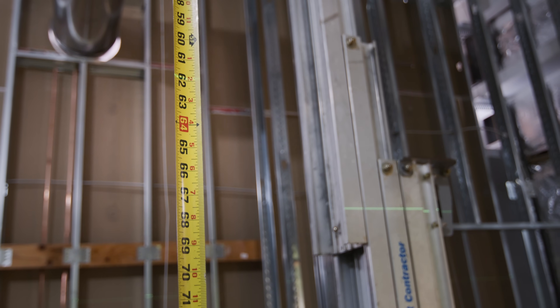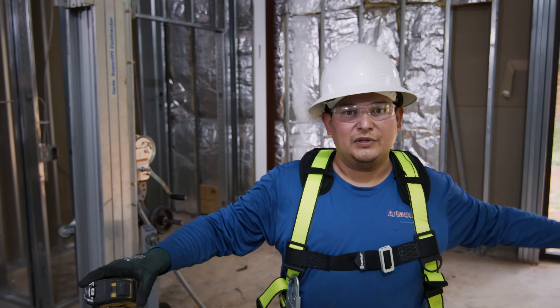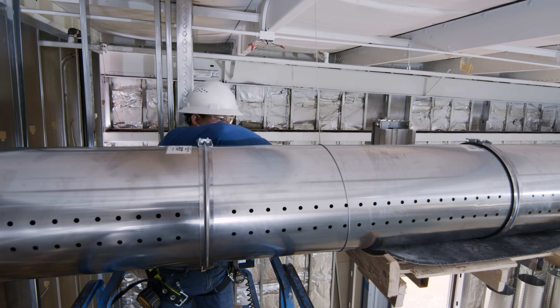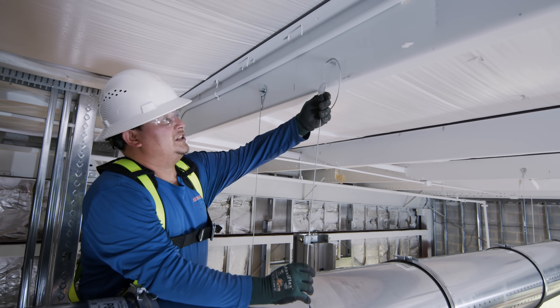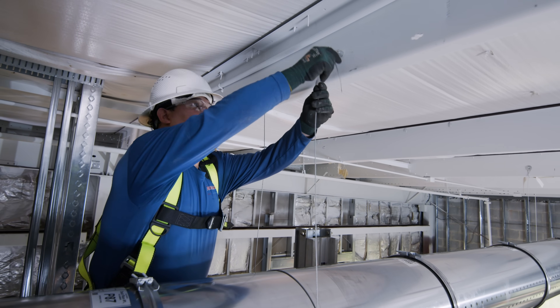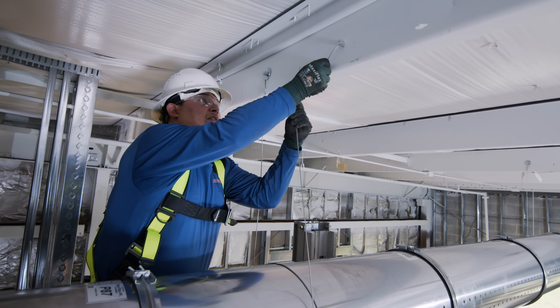For installation it's always better to be on level — it's important that it's going to distribute air evenly in this room as it's supposed to be. We proceed to do a double loop. This cable comes from a Gripple and it's provided by CaptiveAire. All this cable and hardware we're going to find in the boxes.